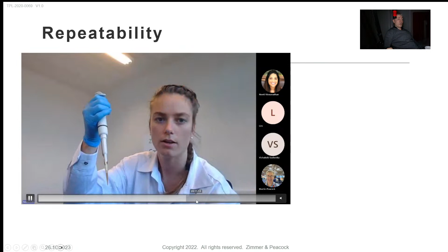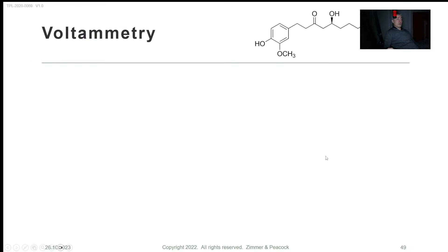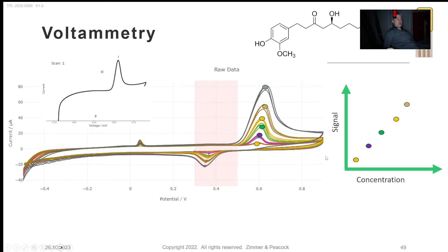And this is because when we manufacture, we test our underlying electrodes by cyclic voltammetry, just so that we can check that things are actually repeatable. And then we test across the batch to make sure that our relative standard deviations are not super high. I mean, relative standard deviations on some screen-printed electrode products are probably like 50%, 100%. We're keeping ours in the single digits. And we do that because we want it for ourselves. And then our business model is slightly unusual in that we also sell them to other people on the web store. So when you see us doing products and signal versus concentration, the only reason we're getting away with this calibration free is because of the reproducibility of the manufacturing process.